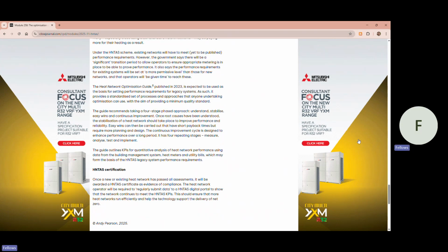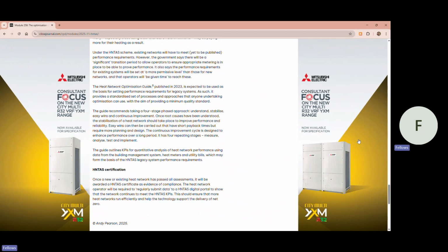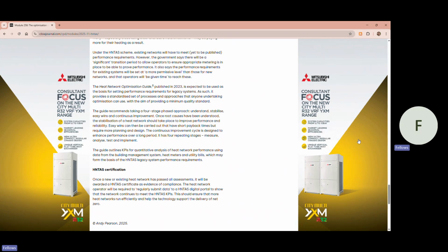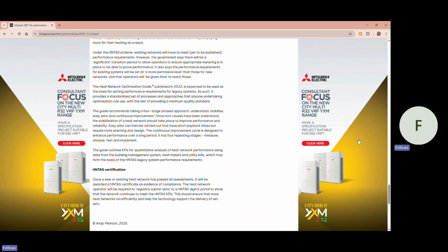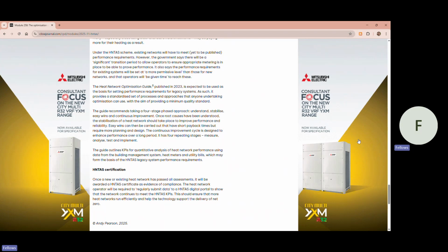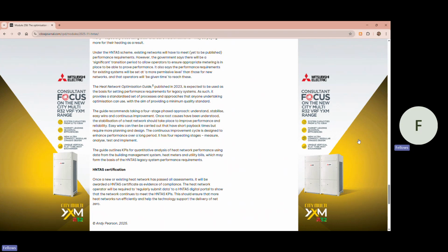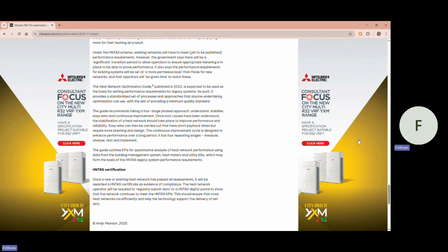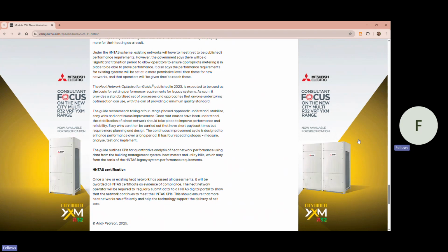The guide recommends taking a 4-stage phased approach: understand, stabilize, easy wins, and continuous improvement. Once root causes have been understood, the stabilization of a heat network should take place to improve performance and reliability. Easy wins can then be carried out that have short payback times but require more planning and design. The continuous improvement cycle is designed to enhance performance over a long period. It has 4 repeating stages: measure, analyze, test, and implement.